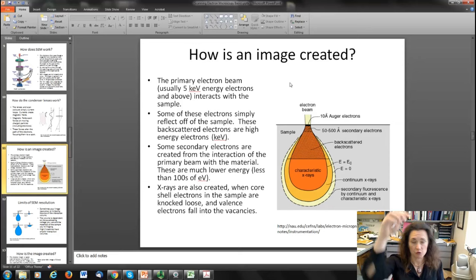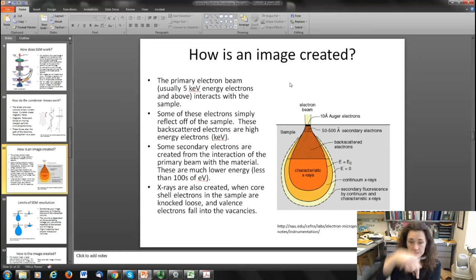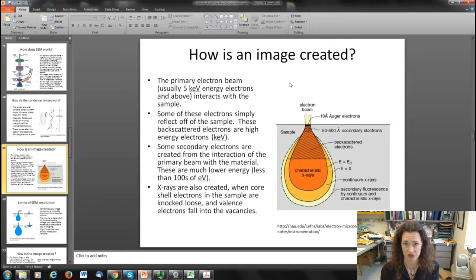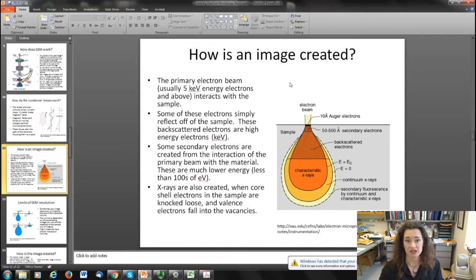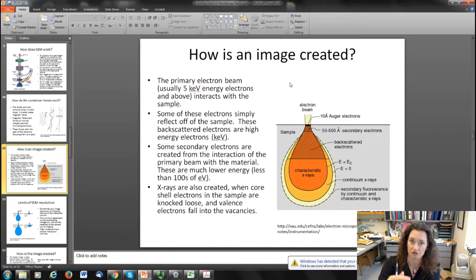Once the electron beam is focused down to a spot and strikes the surface, the image can be created from a number of different signals. The primary electron beam can sometimes just bounce right off the sample — those are called backscattered electrons or BSE. These are high energy electrons and you can use their reflection to generate a backscattered electron image. Another very typical signal is the secondary electron image: secondary electrons are created from the interaction of the beam with the material, have much lower energy (less than about 100 eV), and are knocked loose when the primary electrons hit the surface.